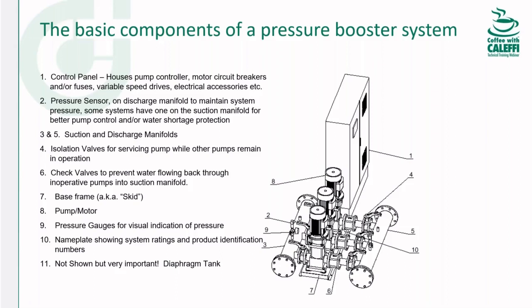And please make sure that you check the orientation of the check valves during commissioning. Many an hour has been lost troubleshooting, only at the end of the day to find out that one of the check valves is backwards. So I would definitely add that to your commissioning checklist.